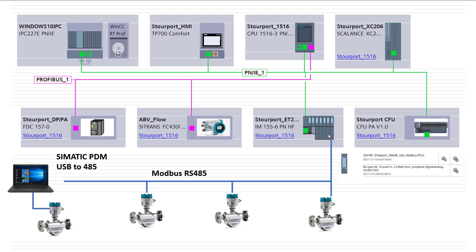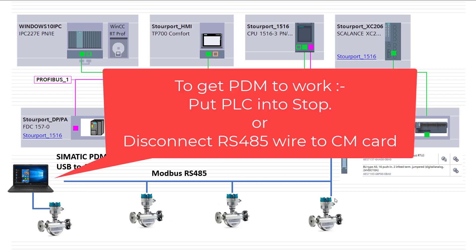It's a slave on the ET200SP rack, and that is a slave to the PLC. So we're not going to affect the comms going to the rest of the PLC, but what will happen is there's no way to distinguish between what Master is communicating first. So what you will see is PDM will probably start to communicate because we're still using cyclic communications here, but as soon as this Modbus Master tries to talk, PDM will time out.